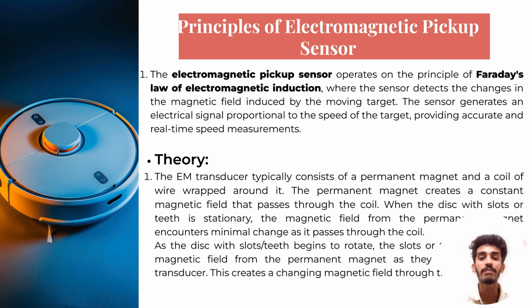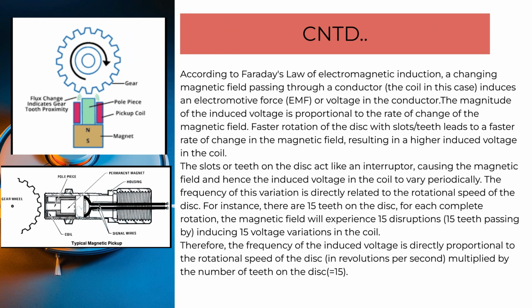This creates a changing magnetic field through the transducer, which, according to Faraday's law of electromagnetic induction, when passing through a conductor, basically the coil in this case, induces an electromotive force or voltage in the conductor. The magnitude of the induced voltage is proportional to the rate of change of the magnetic field. Faster rotation of the disc with teeth leads to a faster rate of change in the magnetic field, resulting in a higher induced voltage in the coil.